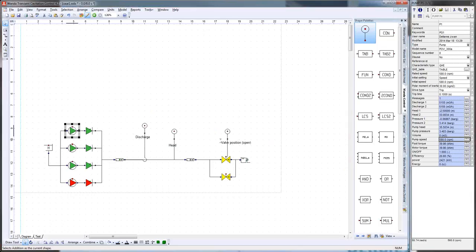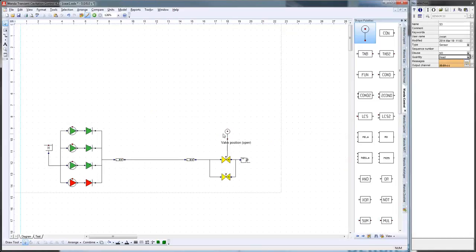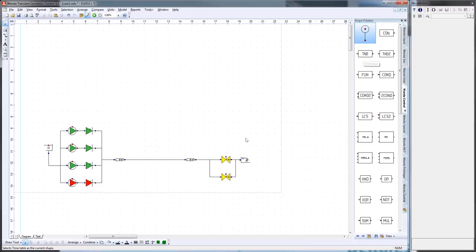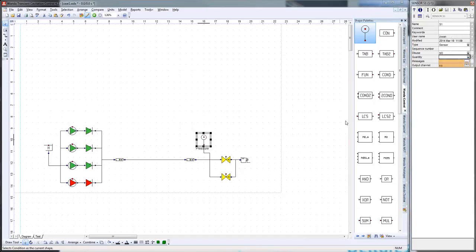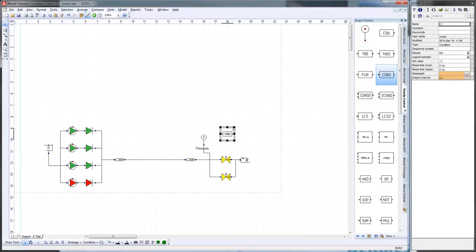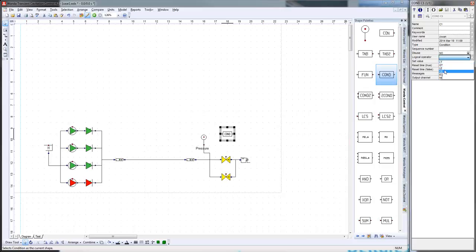So let's now go back to Wanda. I'm going to delete the sensors because I'm not going to need them. Now I want to build a control system which closes these two valves when the pressure here in this node drops below one bar. The first thing I'm going to do is put in a sensor, because I need to measure the pressure there. Second, I need a signal which becomes true when the pressure drops below one bar, so that's why I can use a condition. In this condition, I can choose the logical operator - less than, greater than, less equal, greater equal, equal, not equal. In this case I'm going to say less than. Then I need the value, so that's one bar, which is 1E5 Pascal, because it's an SI unit.